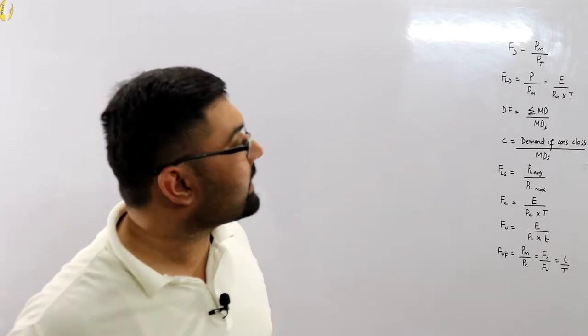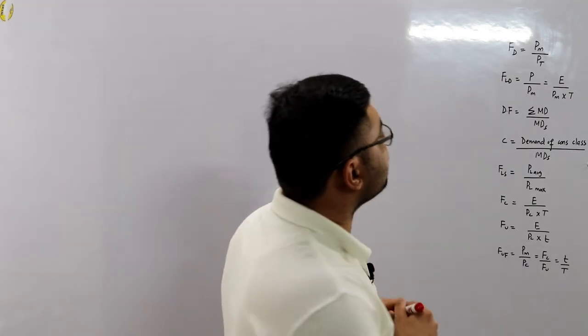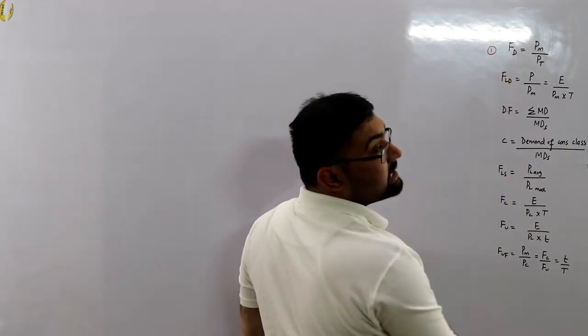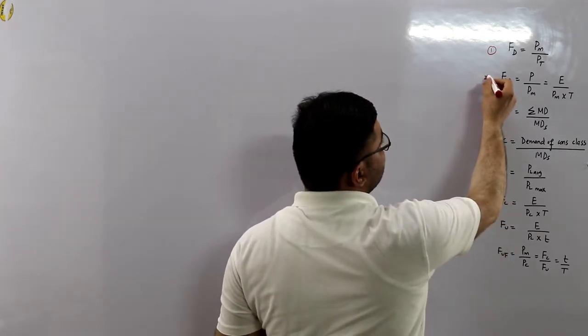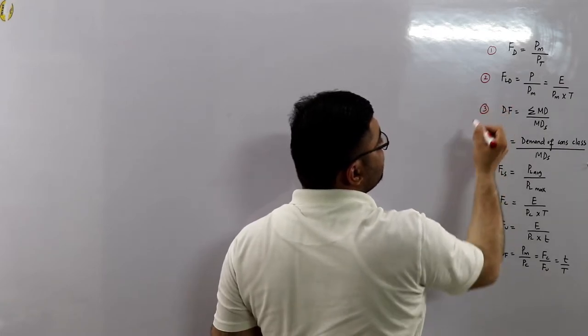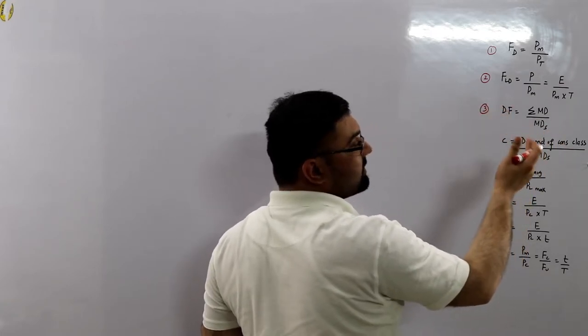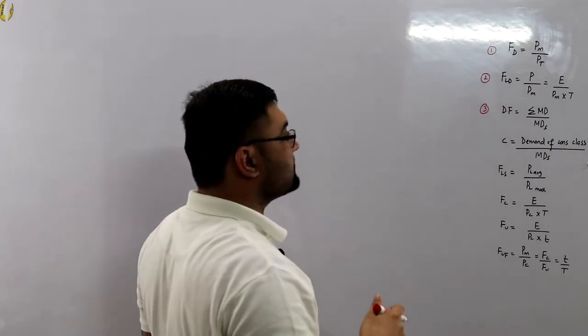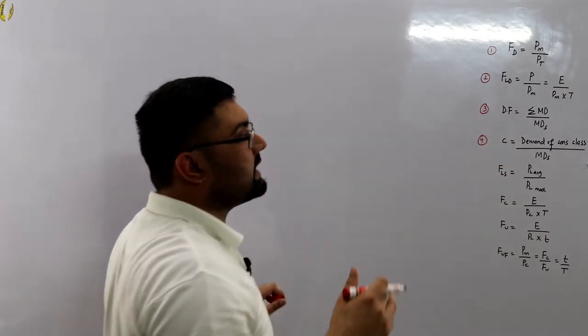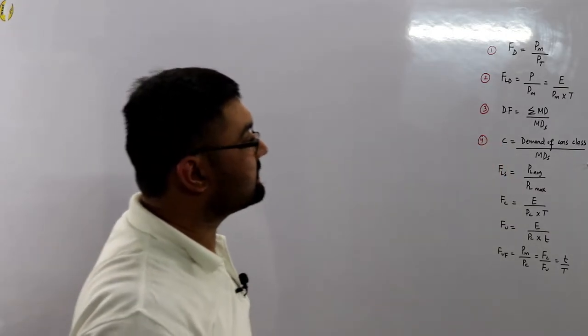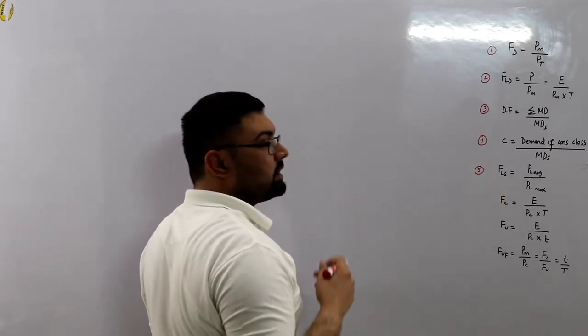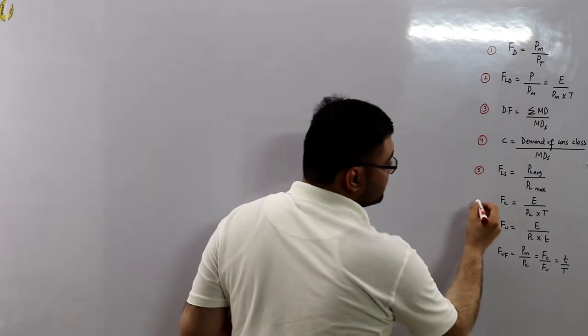Number one is the demand factor — maximum demand on the connected load. Number two is the load factor — average load to the maximum demand. Number three is the diversity factor — summation of the maximum demands of individual consumers to the maximum demand of the system. Number four is the class contribution factor — demand of a consumer class at the system peak divided by the system peak. Number five is the loss factor — power loss at the average load divided by the power loss at the maximum load.